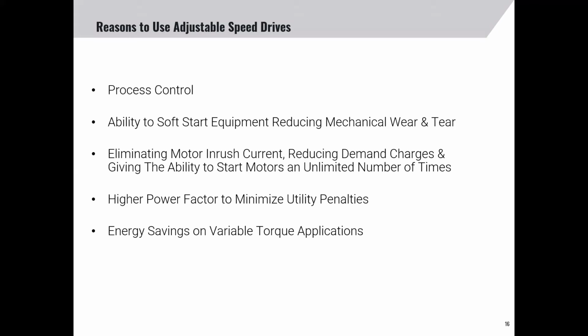Another advantage of using an adjustable speed drive is that you can have as many starts as you would like with an electric motor, because you don't see any heating going into the rotor of the motor, because you're accelerating the motor starting from 0 voltage and 0 frequency. Another advantage is that the system has a power factor to minimize utility penalties. If you opened up a variable frequency drive, you would see many capacitors in there that are actually working to increase the overall power factor of your system.